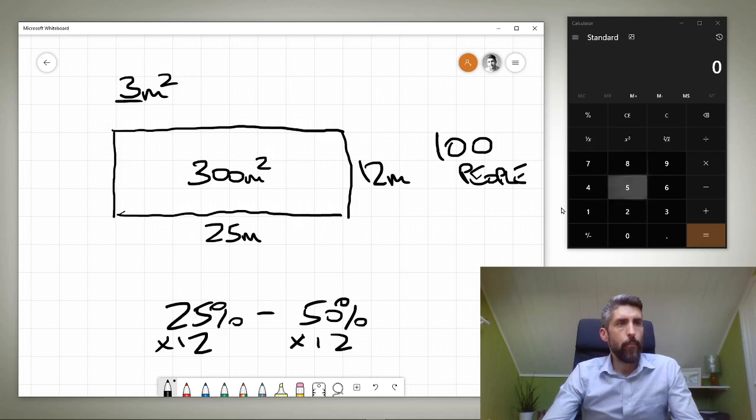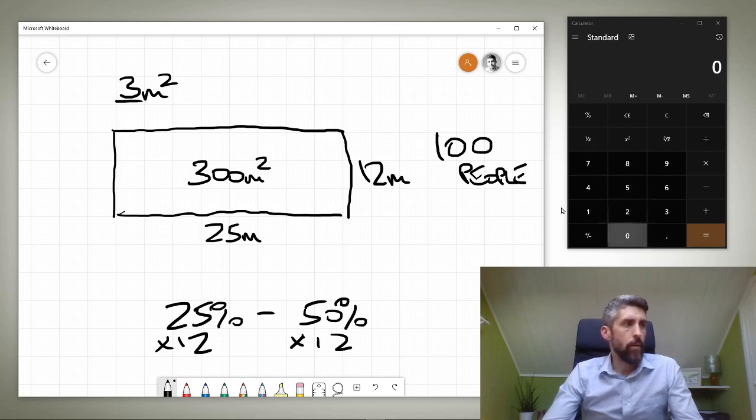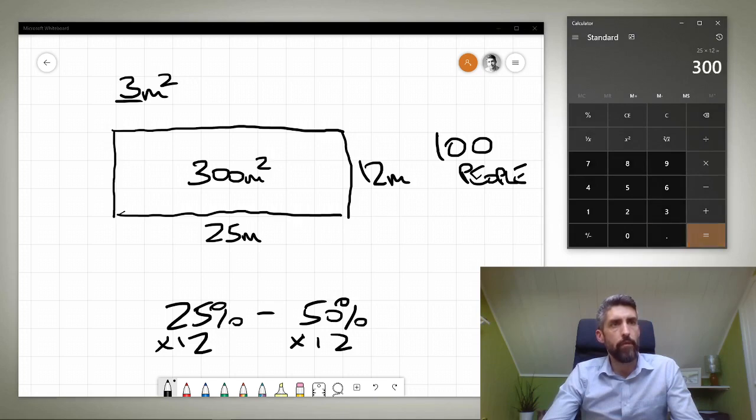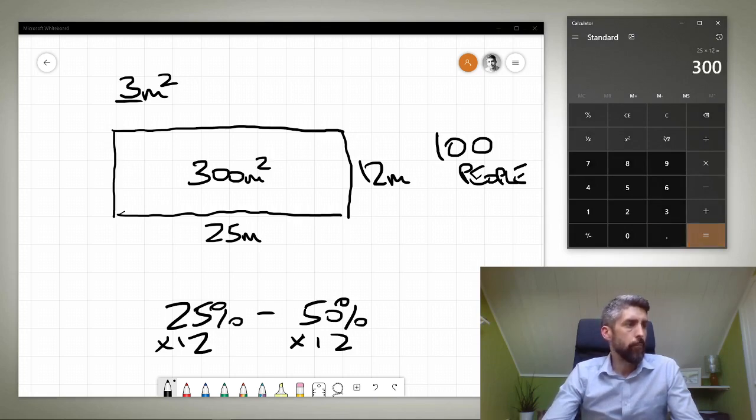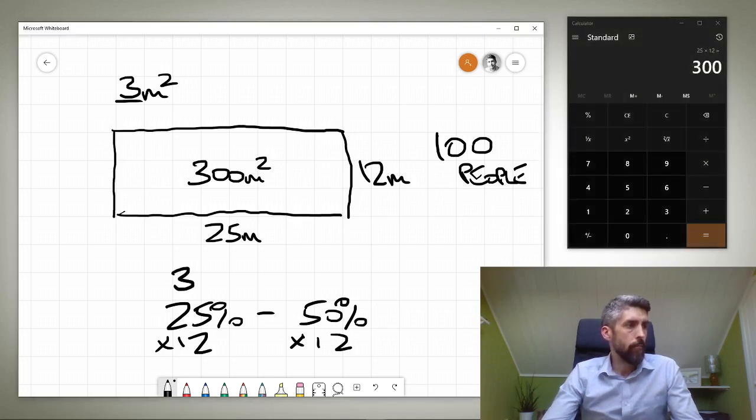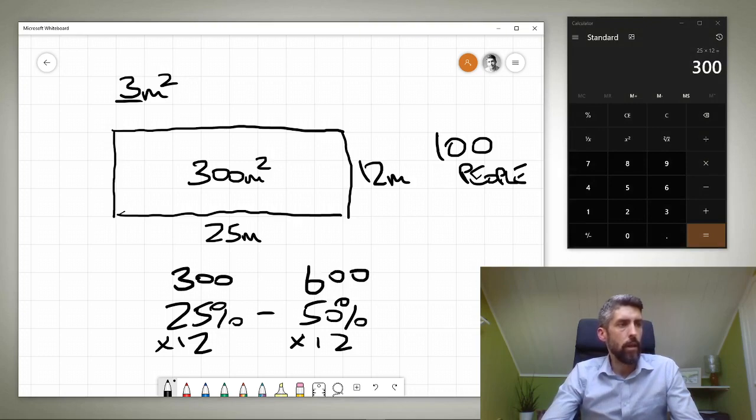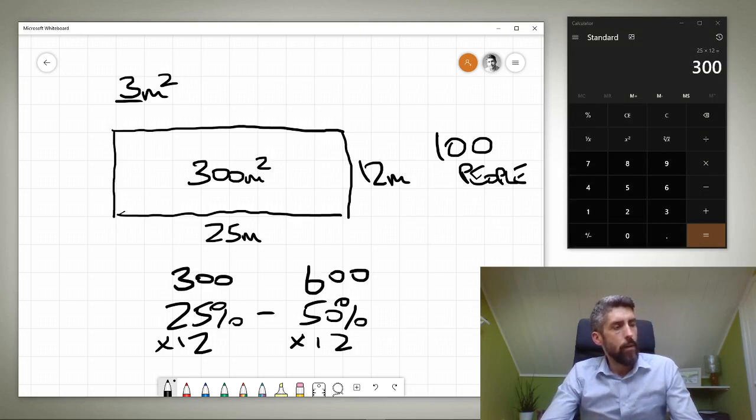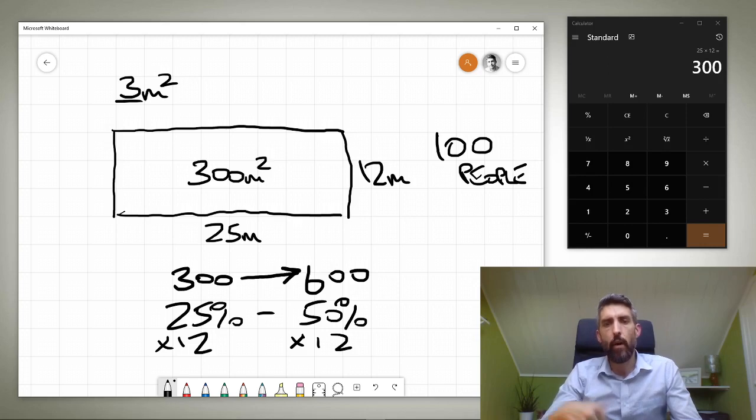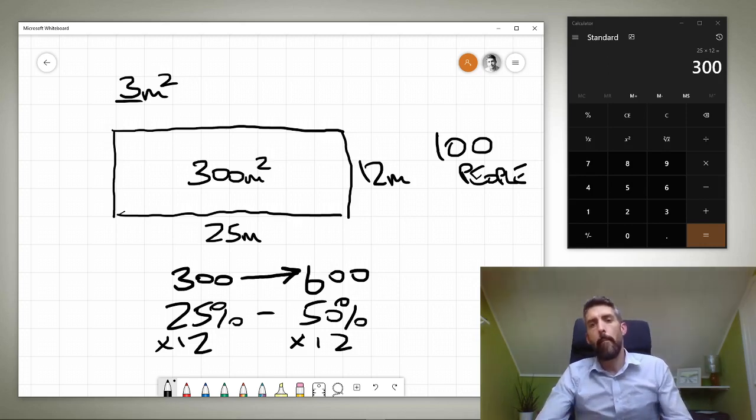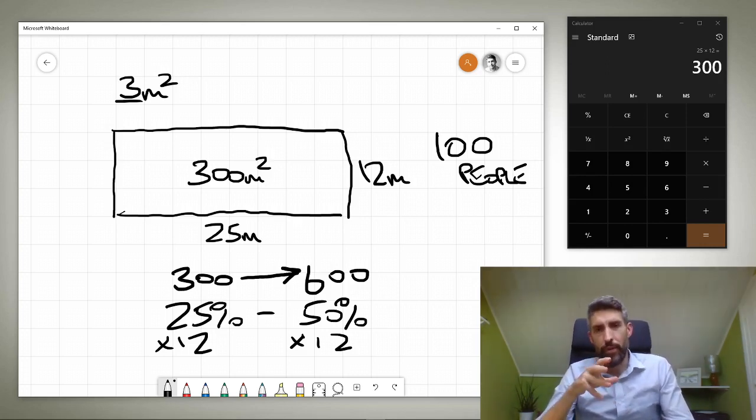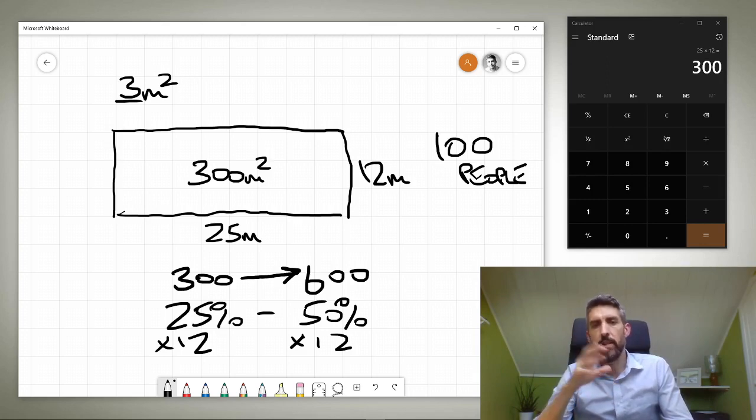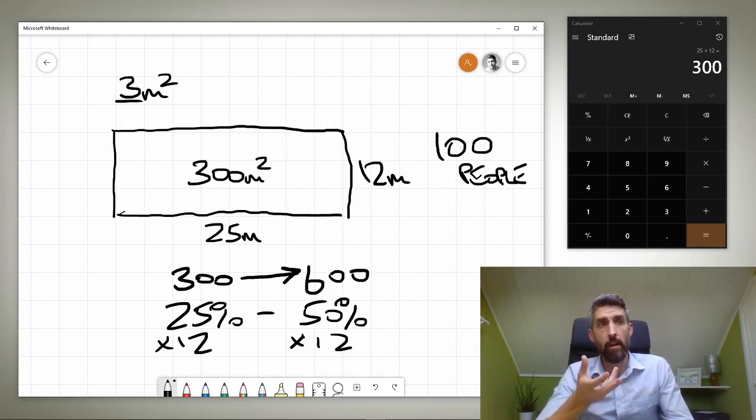So what have we got now? 25% of 100 is obviously 25, multiply that by 12 and you've got 300. 50% of 100 times by 12 is going to give you 600. So this particular pool with dimensions like this could have between 300 and 600 people using it on a daily basis, and what you'd need to do is again use this as a starting point, as a guide.